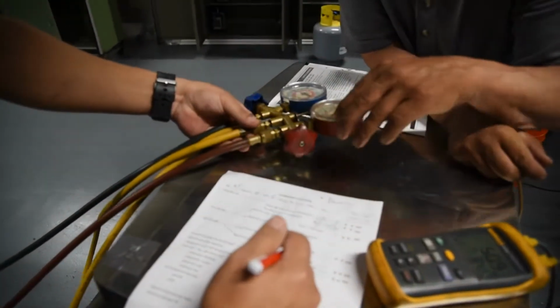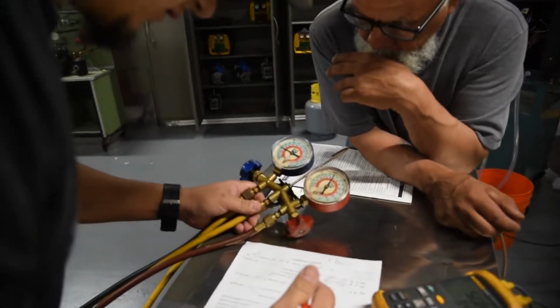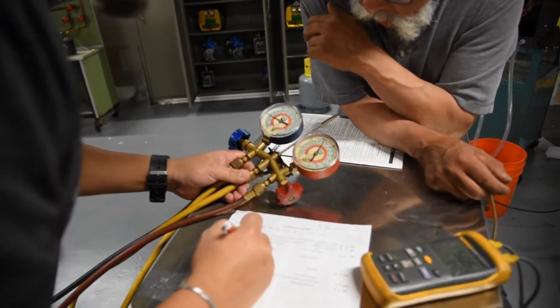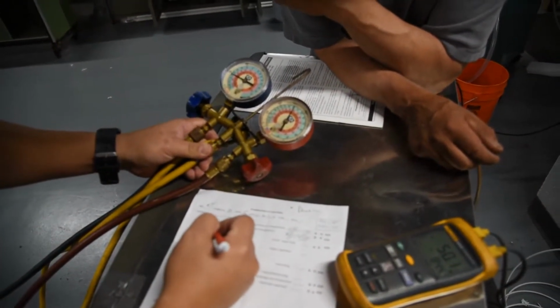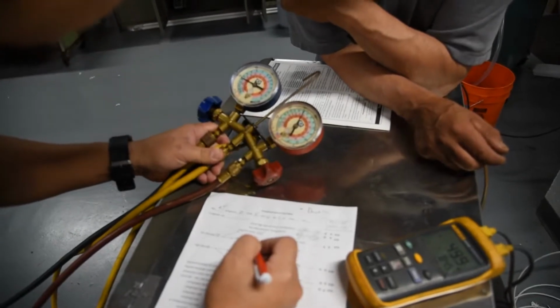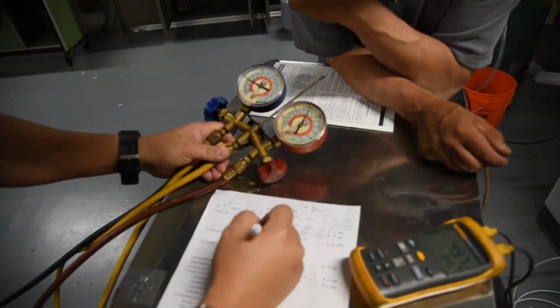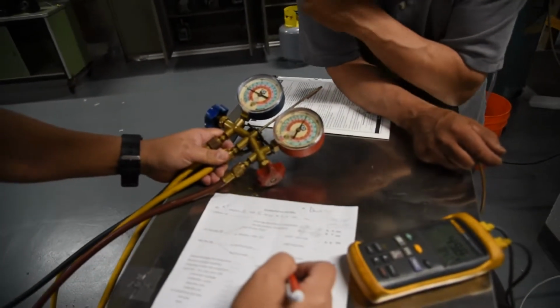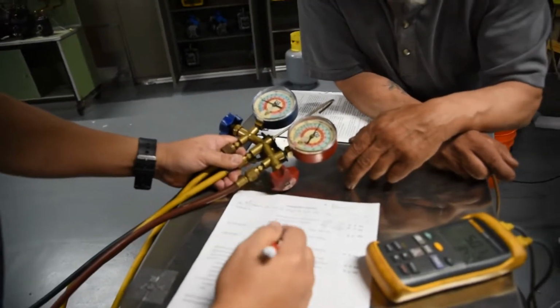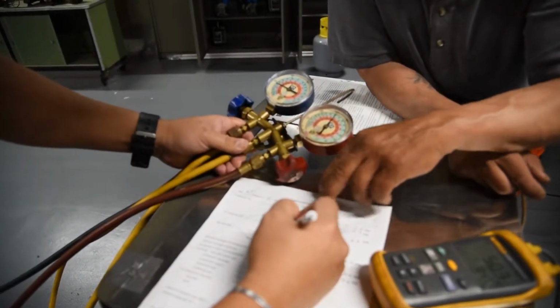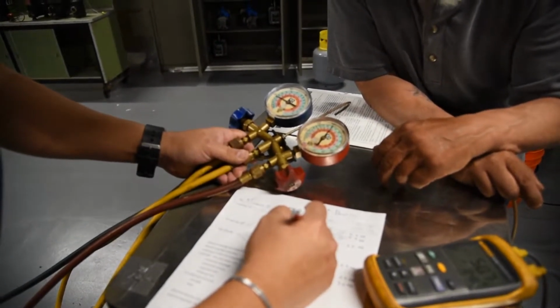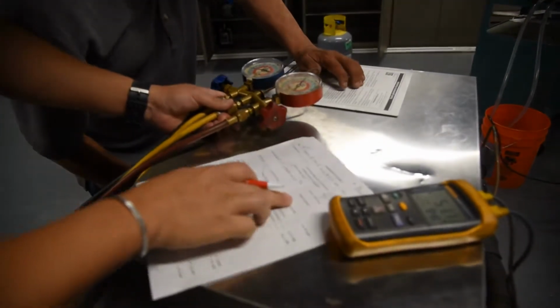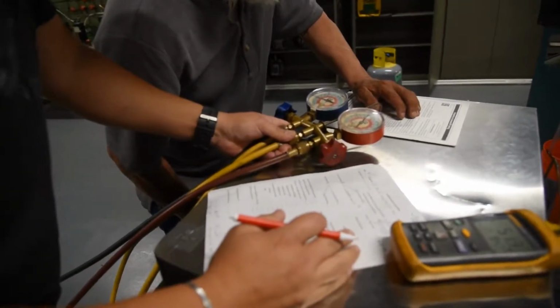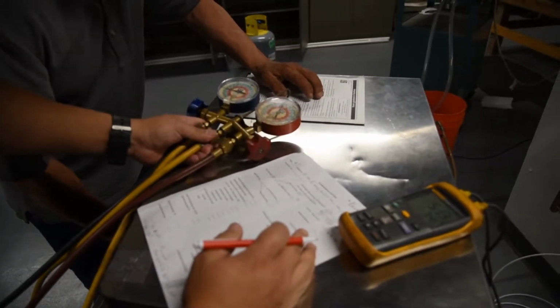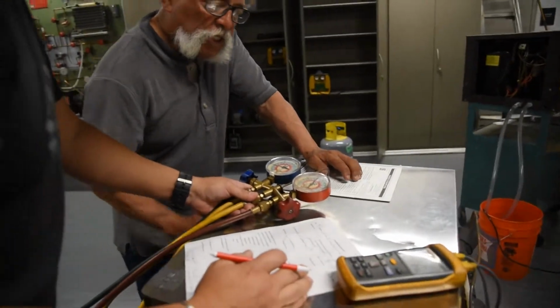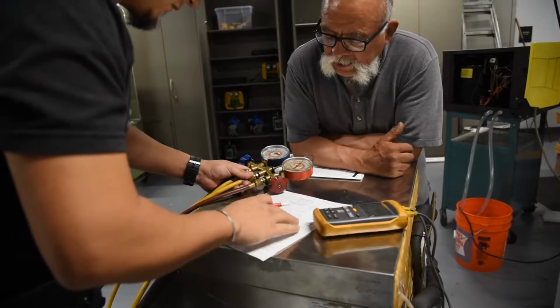And the low side pressure. Our low side pressure in PSIG is going to be 48. And our PT chart is telling us that we're about 4 degrees. Okay. Now on the high side, now we subtract, correct? 4 from 50, so we have 46. That's pretty hot. High superheat means there's low refrigerant. Okay, let's just check the subcooling and see if that indicates the same issue.